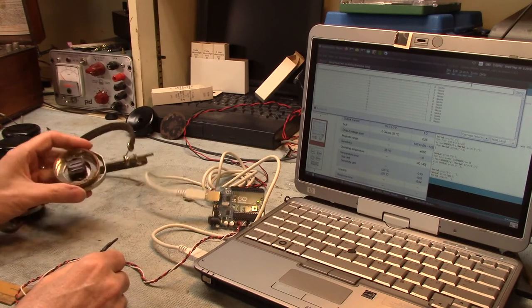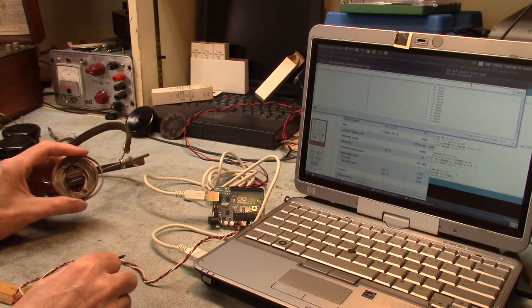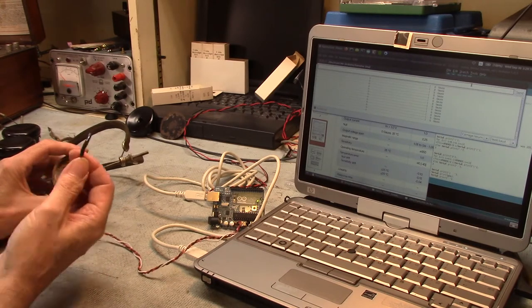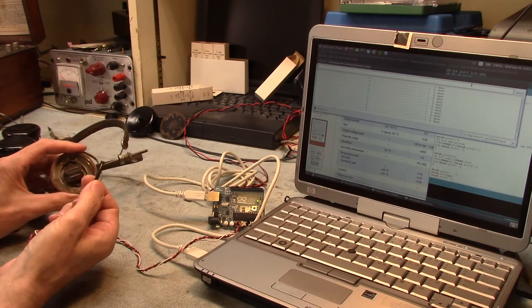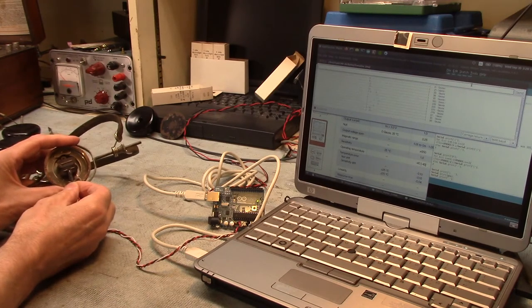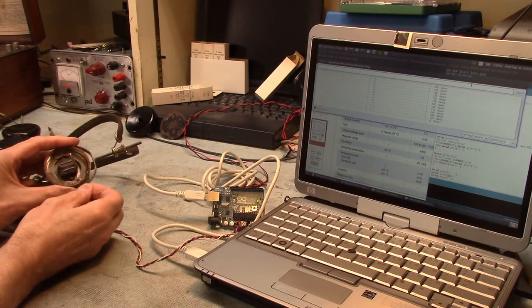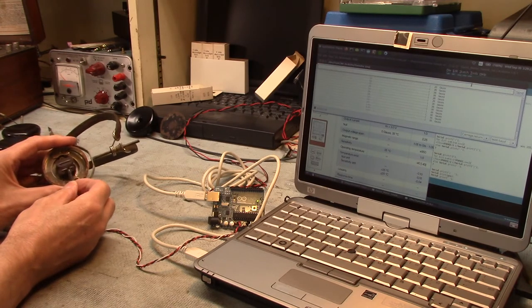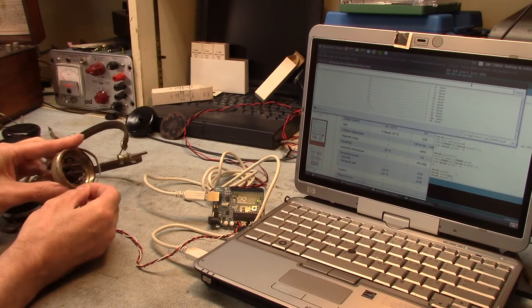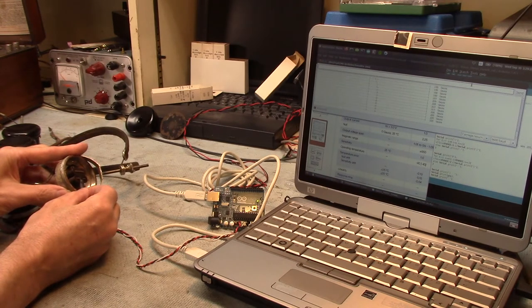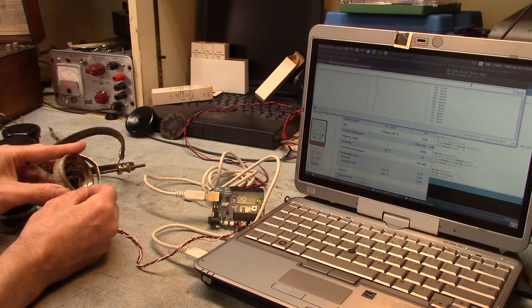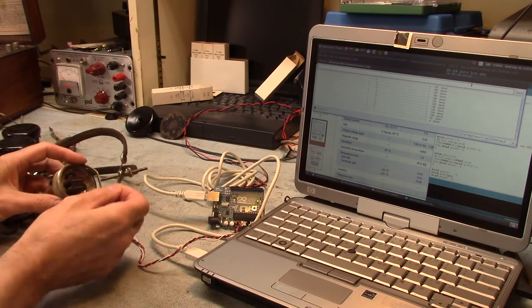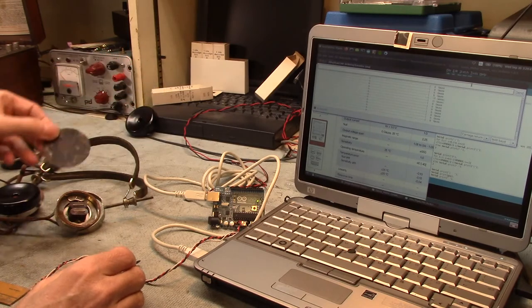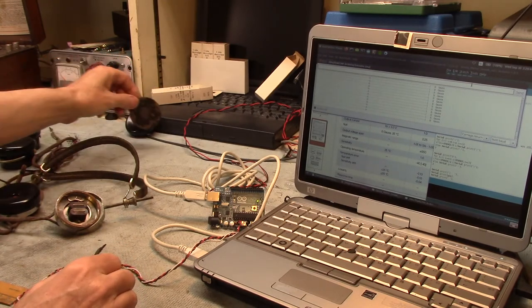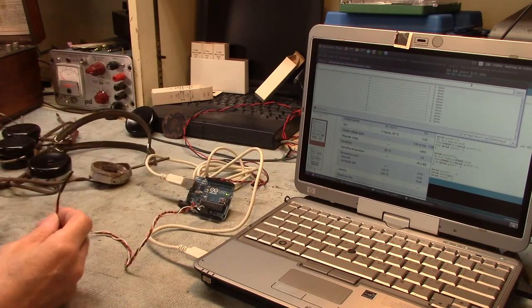So that's something to take into account. When I oh so confidently said it was 100 Gauss, it was 100 Gauss at the distance of the plane of that sensor, which is different from this sensor. It's something to account for. It's 100 Gauss where it was measured, and what I really care about is the distance to this diaphragm. If I was to eyeball where the diaphragm is, which I can't really quite get to here, I know it's only about 12 thousandths off. Just eyeballing it down there, I might say the plane at which this diaphragm is actually interacting might be 200 Gauss. So it's something to think about when you're doing measurements with a Gauss meter.